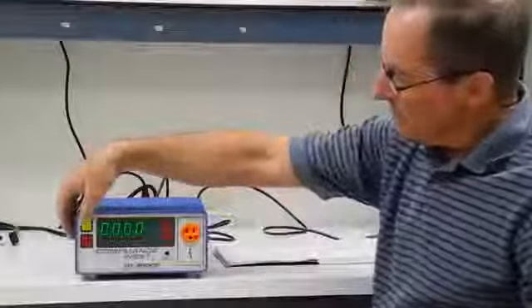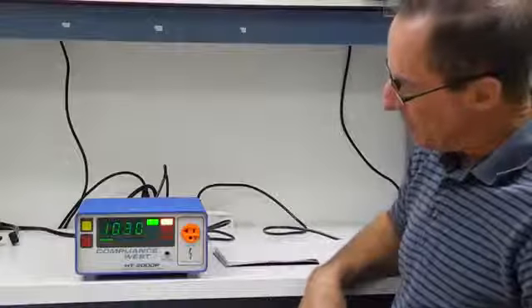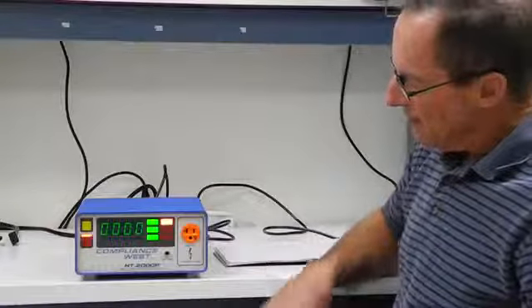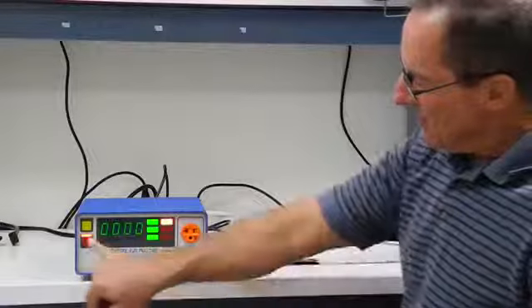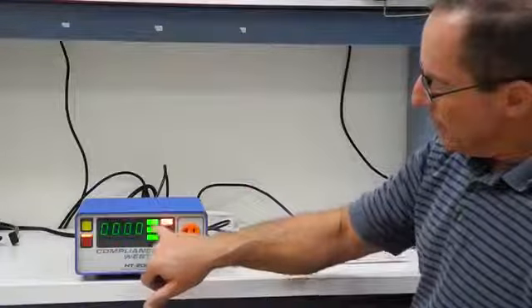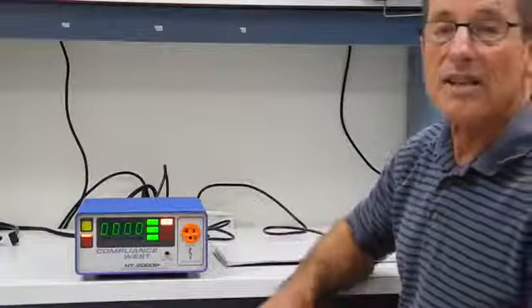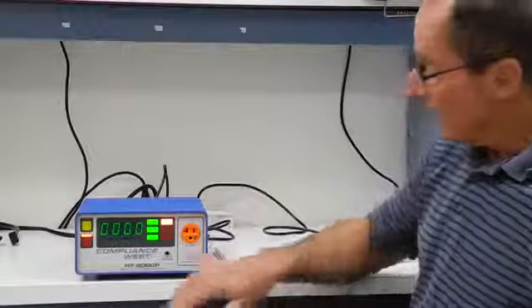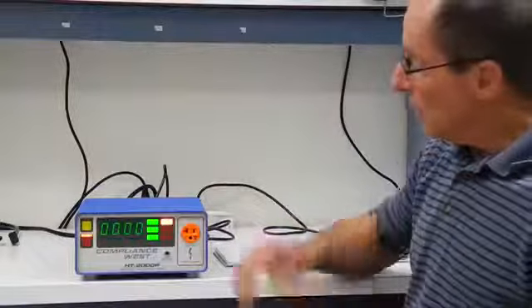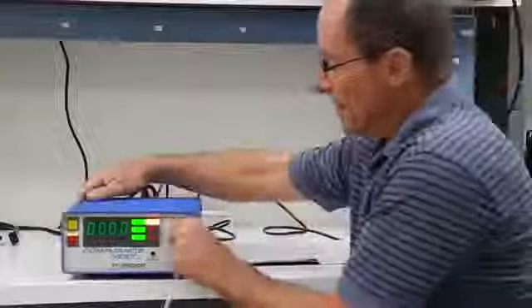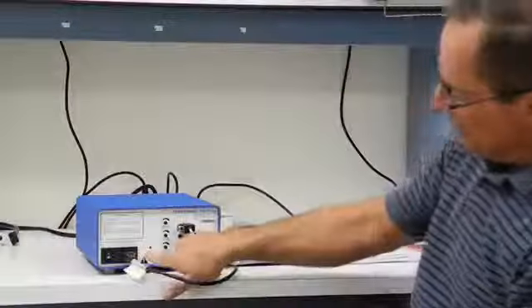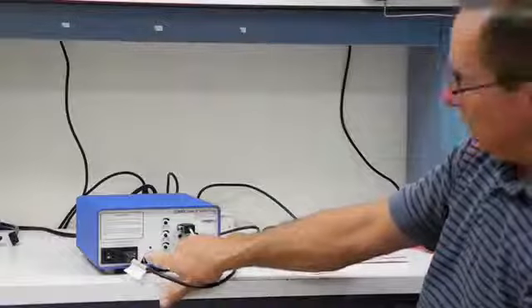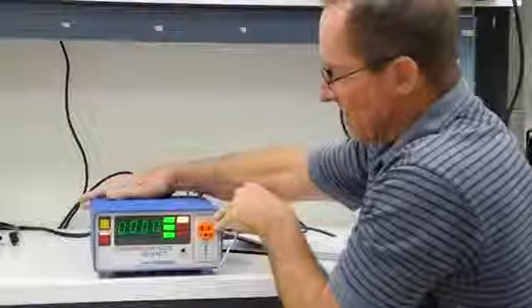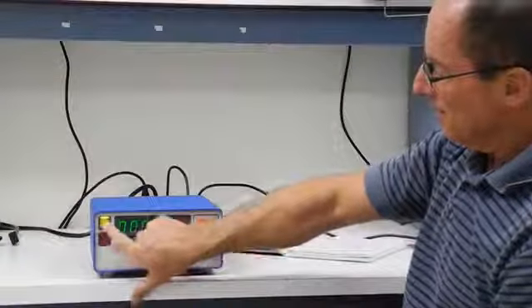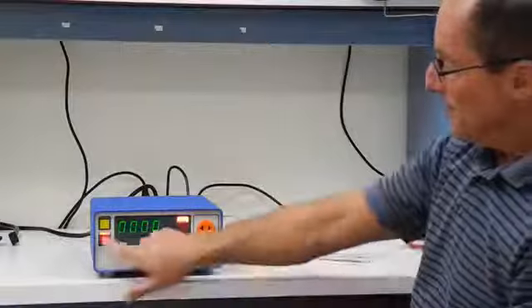So here we go. Push the test button. Ramps up to 1200. That's it. You get all passes. Right now, the ground check and ground open lights are lit because the continuity check is not being done, so that I can do it with nothing connected. But normally you would set the continuity check with this little switch here called ground switch, ground check. You put it in the on position, and obviously we're going to have a failure when we run this. That shows ground open.